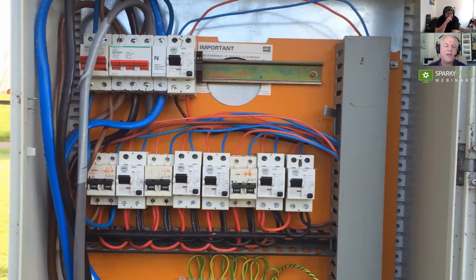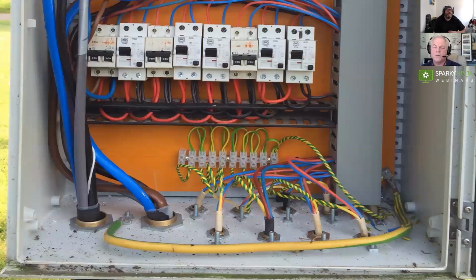So overcurrent protection on half of those outgoing supplies is non-existent. They're going onto armoureds, which are then going down through the ground and then going out to feed caravans through the ground. So what if somebody hits one of those cables? Right, so if you strike a cable...